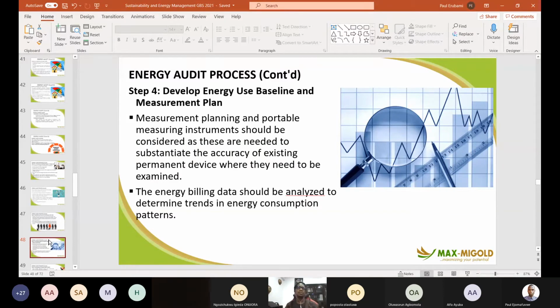Take your air conditioning system, for example. When the compressor is on, the AC is trying to saturate the cooling to the thermostat setting, so it runs at very high energy consumption. Once the temperature is reached, the compressor shuts down automatically, and consumption drops dramatically—sometimes to 20%, 30%, or even less. So if that's the moment you use your clamp meter to get an amperage reading, you're making a big mistake.